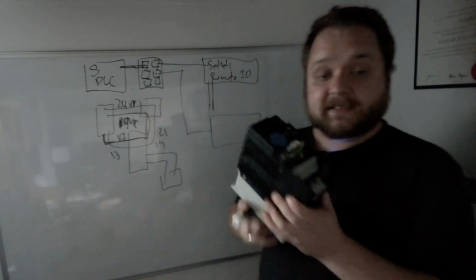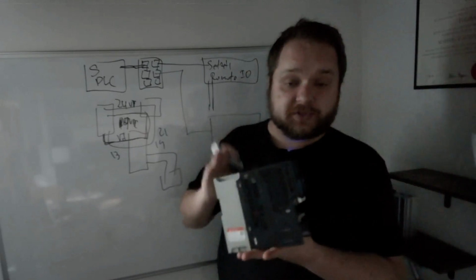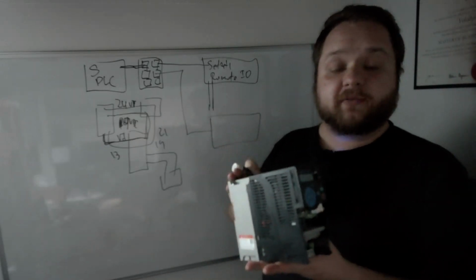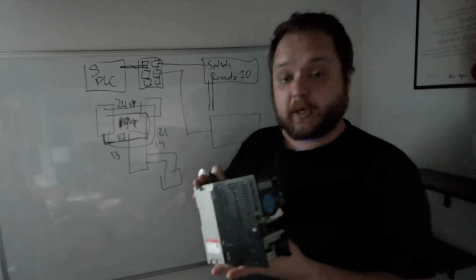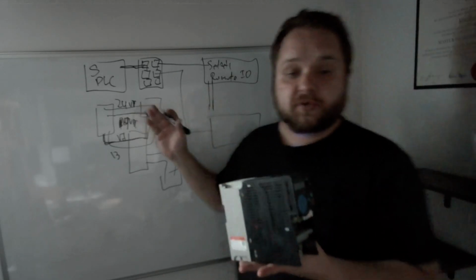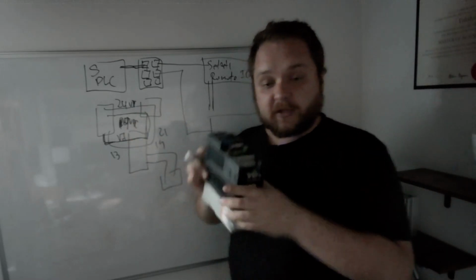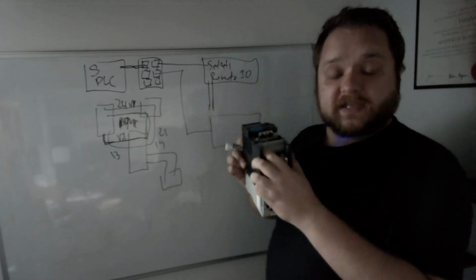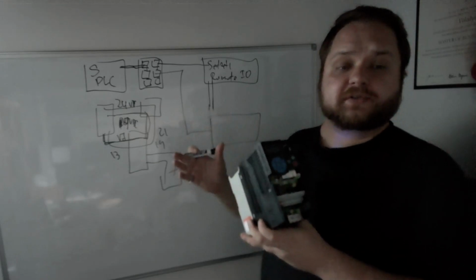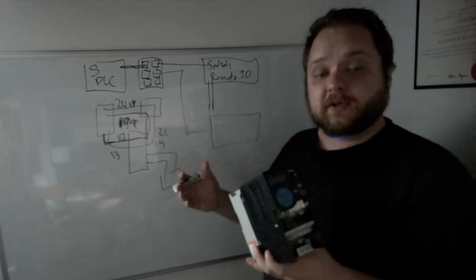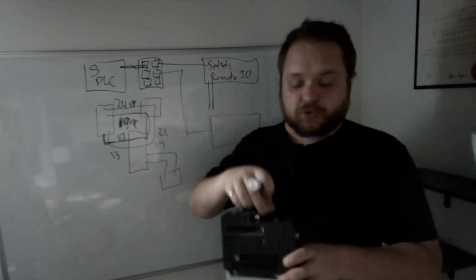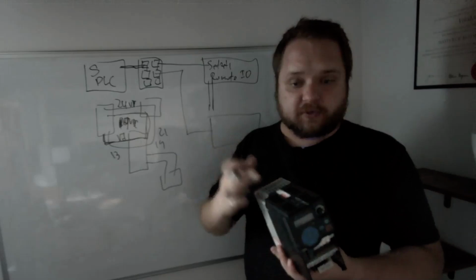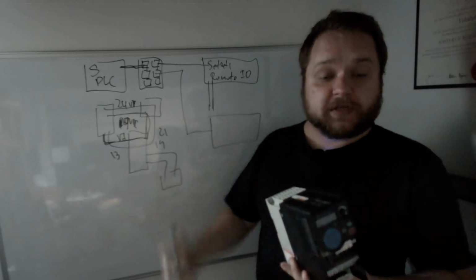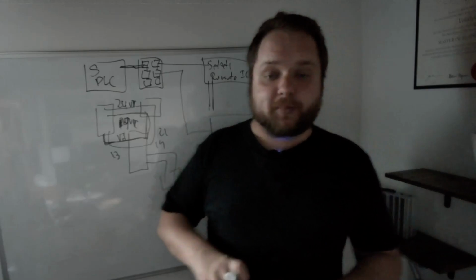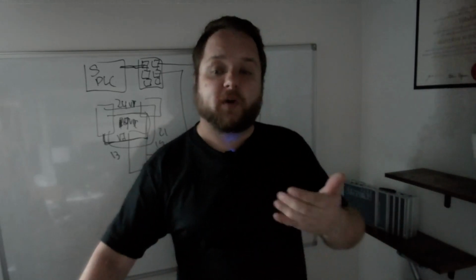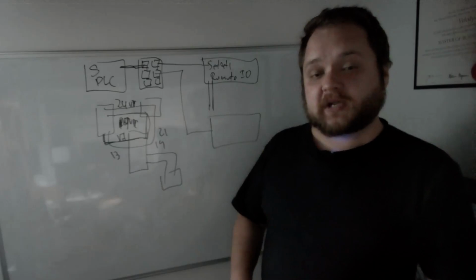The last mention is that the devices usually attached to your safety circuits do not come pre-configured with those safety features out of the box. So just as you need to set up and make sure that the relay circuit is correct, remember that on the PowerFlex, you will have a jumper on the safety side, but you also have certain faults and you have certain features associated with the failure and how safety is handled when you drop the voltages on that side. In some cases, it's going to be an error. In other cases, maybe you need to coast the drive to a stop. So you need to also pay attention as to how you're handling once the circuit is no longer safe on the output side of your safety relay.